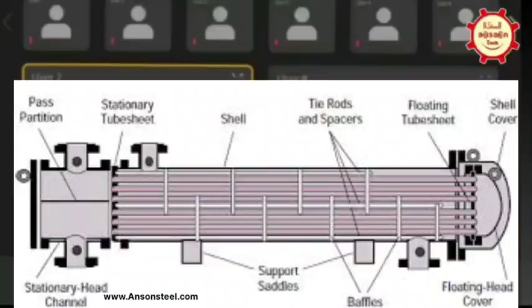Yes sir, so I have a floating type heat exchanger. Both sides are 16 bar and 200 degrees Celsius temperature. Shell side also 16 and tube side also 16. Temperature also same, right? Okay, in tube sheet load case number 6, we have to do 3 corroded case and 3 uncorroded case - D1C, D2C and D3C.